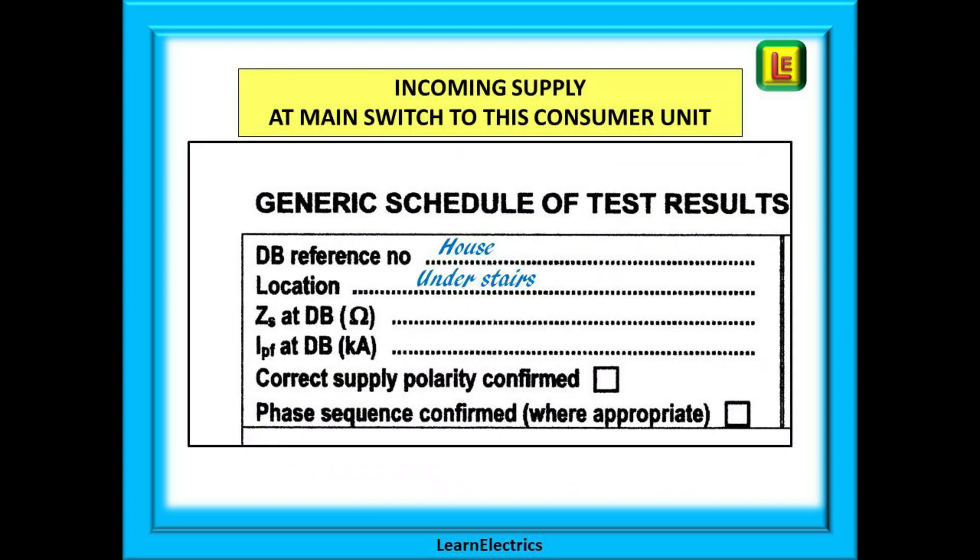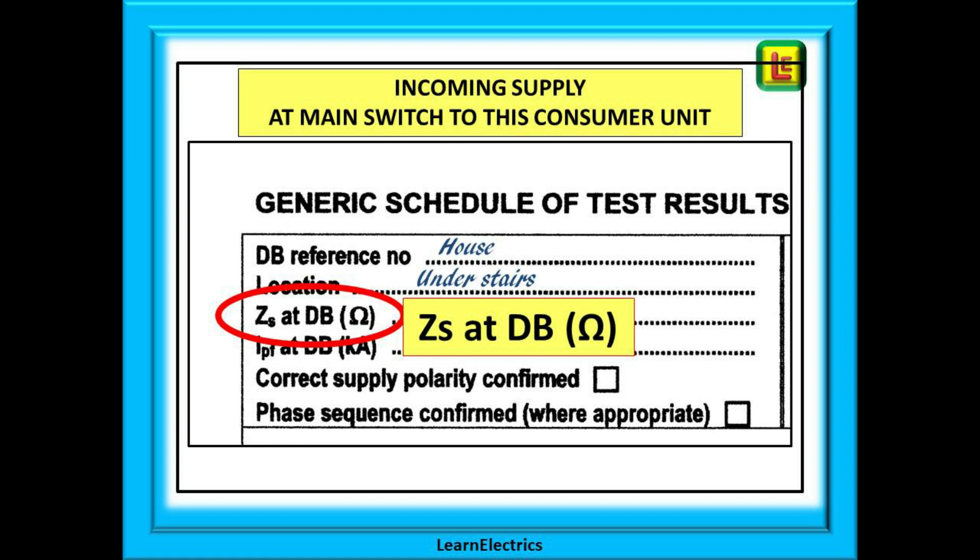Let's begin and we will complete this schedule with examples as we move along. Top left we must enter details of the incoming supply at the main switch for this board. What is happening at this main switch? That is the question. So DB reference does this distribution board or consumer unit have a name or a reference number? In a factory it may well be listed as DB4 or canteen or some other way of identifying it. In a house it may well be the only board so calling it house will be fine. Next where is it located? Under the stairs, in the kitchen, the hallway, wherever. Now we've come to an entry that confuses a lot of people. It says Zs at DB but everyone shouts we always put ZE in there. So a little explanation.